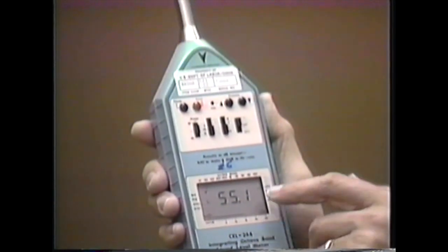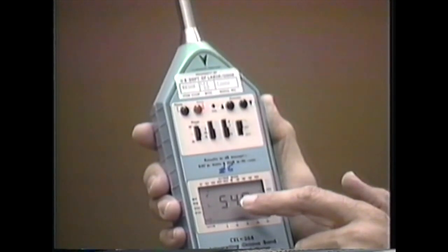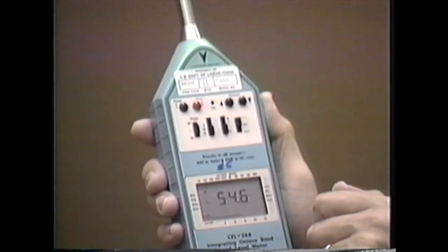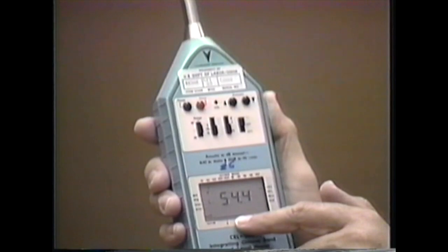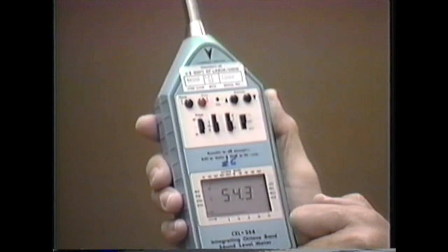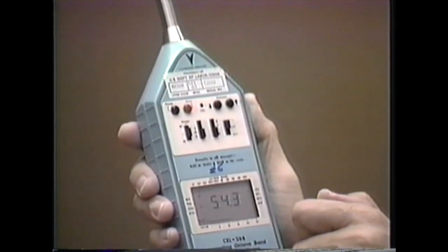When we're doing octave band analysis, typically the digital readout here is an LEQ, so it's a form of moving average. The lower hatched line, dashes, is the instantaneous readout. For the most part, you'll probably want to go with the instantaneous readout, and that is a more realistic measure and it will not have some of the problems that you have with trying to read the LEQ.